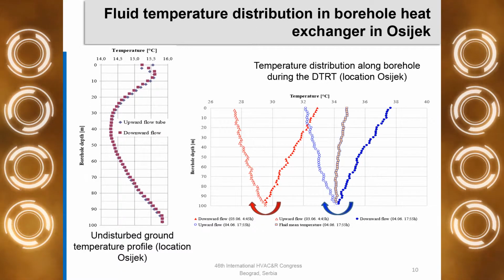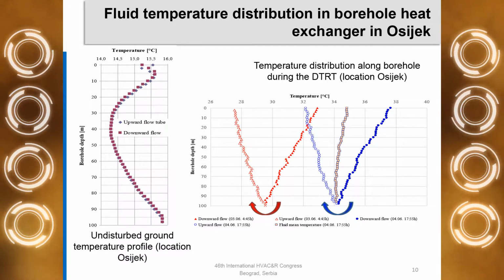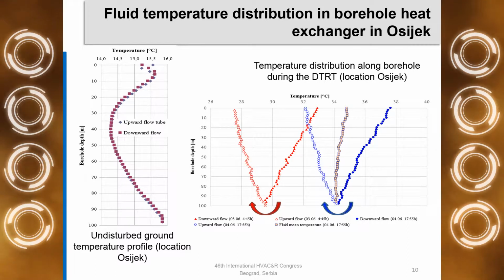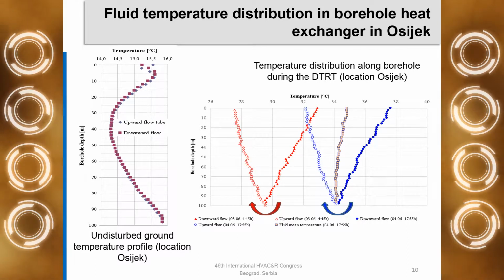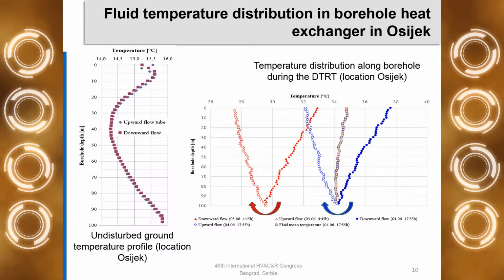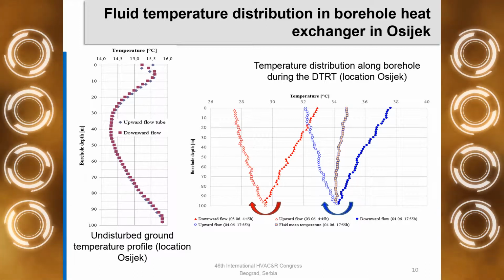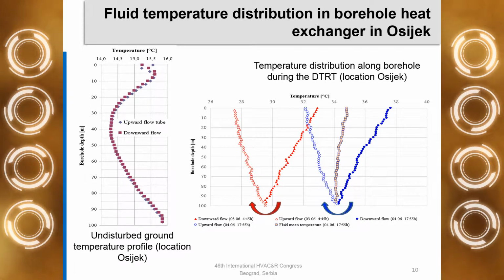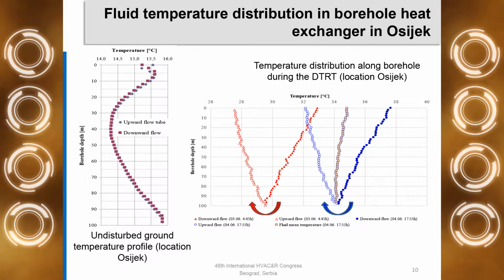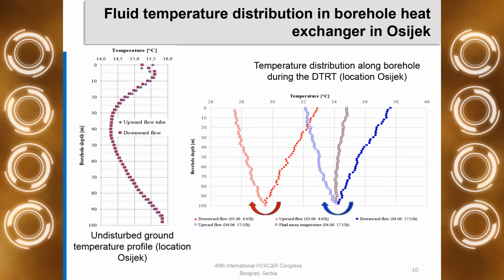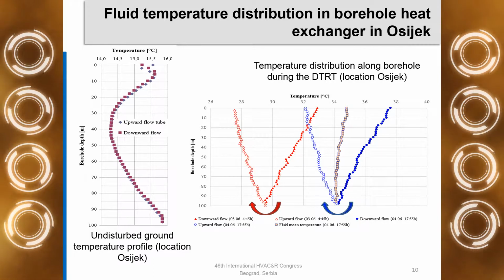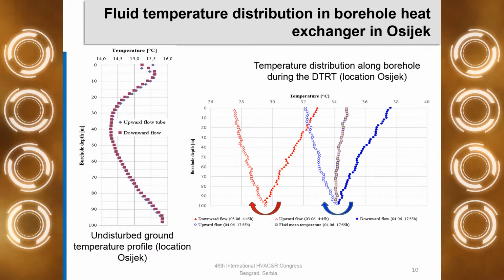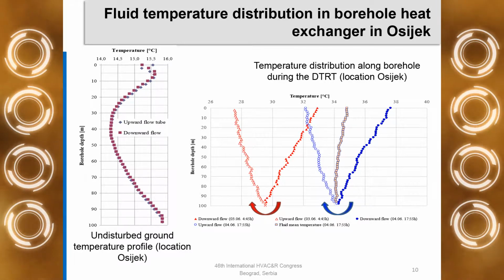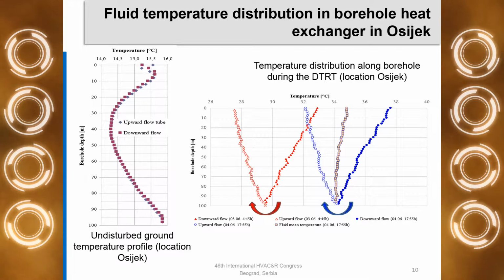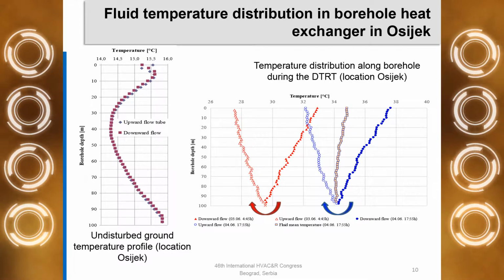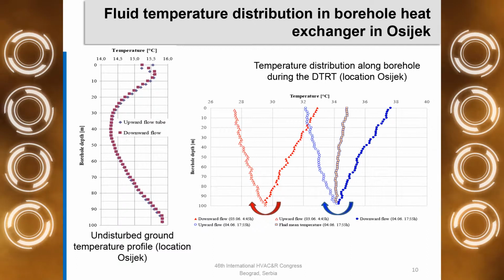Here you can see the first location of the project, in Osijek, around a 1.5 hour drive from Beograd. We can see on the left side the undisturbed temperature profile. The average temperature in the underground was around 15 degrees Celsius. And on the right side, we can see the fluid temperature distribution inside the borehole heat exchanger in 2 different phases of the thermal response test. Also here is plotted the average fluid temperature inside the borehole. This is the fluid entry, and this is the fluid outlet.